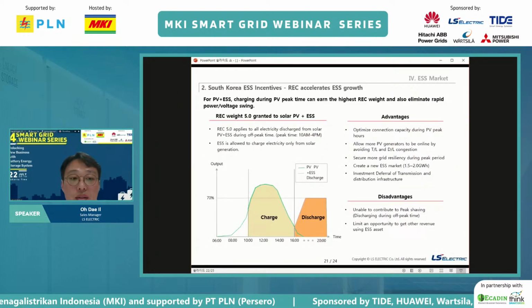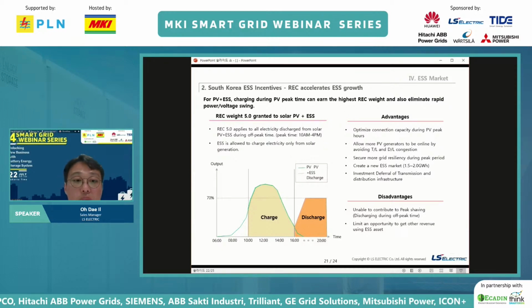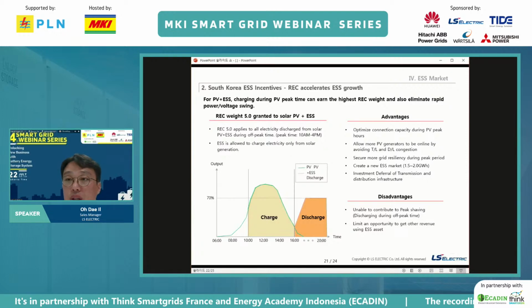As you can see in this graph for PV and ESS, charging during PV peak time can earn the highest REC weight and also eliminate rapid power voltage swing. It optimizes connection capacity during PV peak hours and allows more PV generators to come online by avoiding transmission line and distribution congestion.